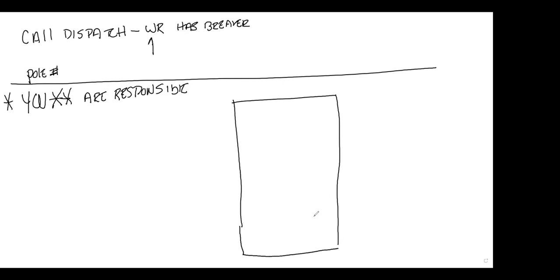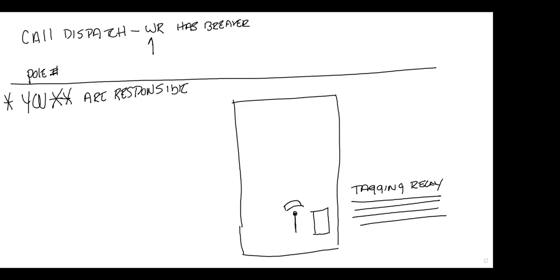I won't draw all the relays in. Obviously, it's got something to do with the reclosing relay, right? What relay was over here with the handle on it that turned orange? Anybody remember? Yeah, it was the reclose relay had the orange. Okay. The reclosing relay just looks like a normal relay. I'll show you some pictures here in just a moment. Sure. But right beside it, I had an orange flag came up when I turned the handle. That was called the tagging relay. Oh, okay, the tagging relay. Tagging relay, right. Now, if it's orange, there's a hotline work permit.